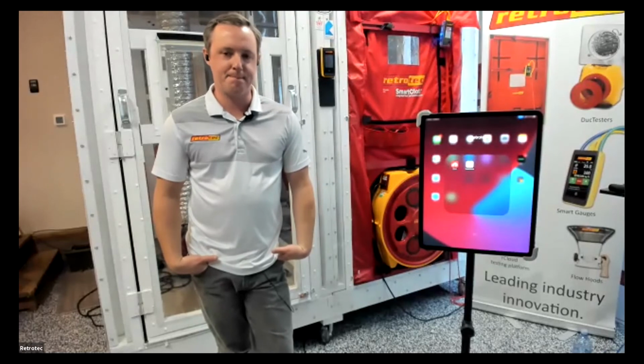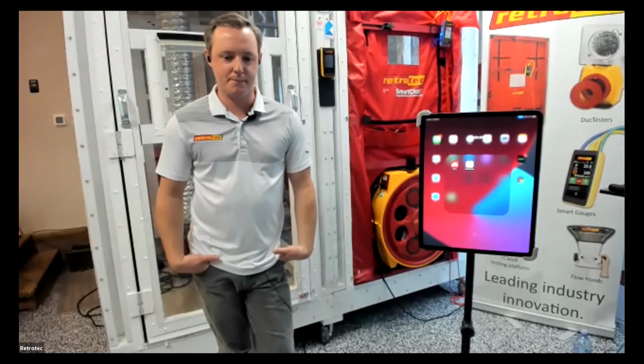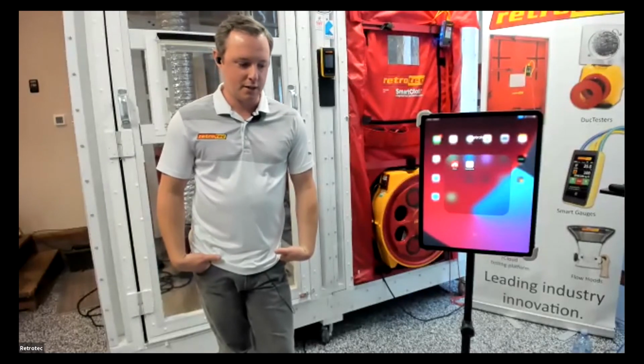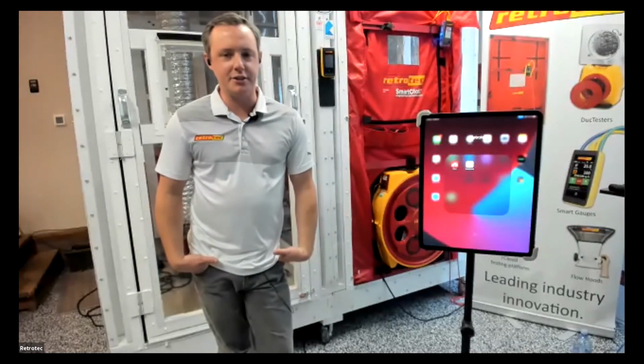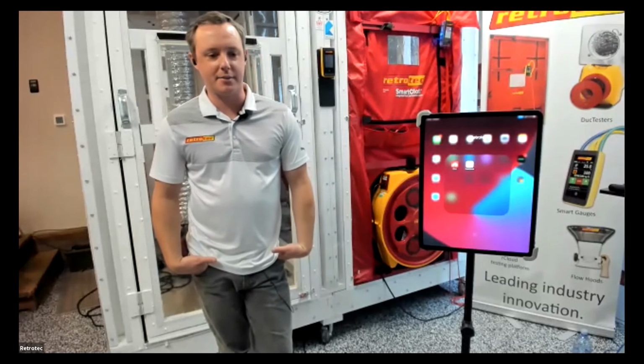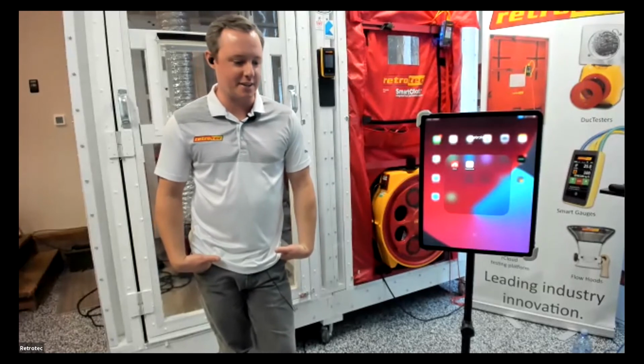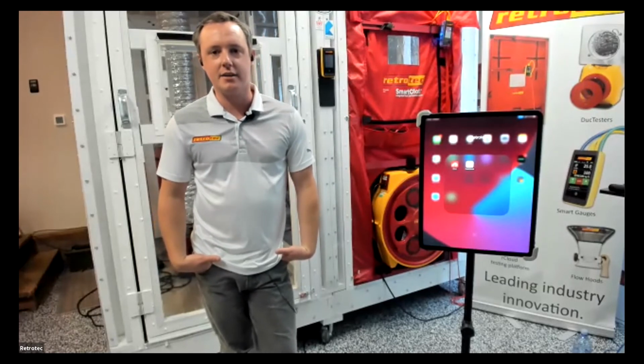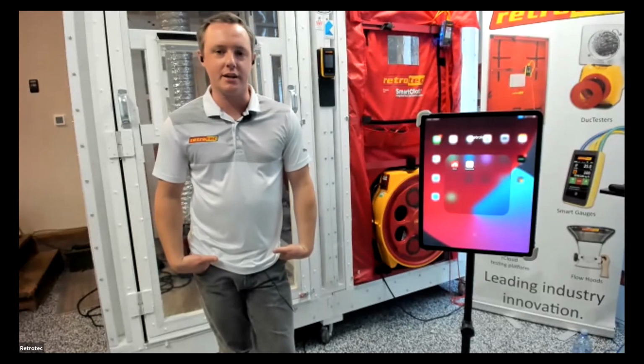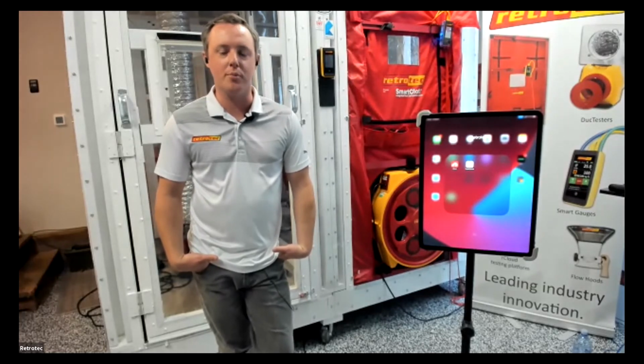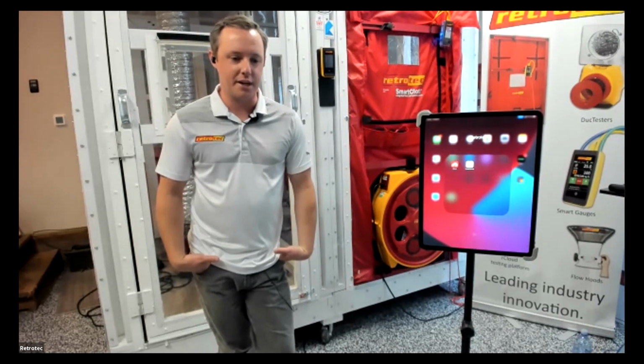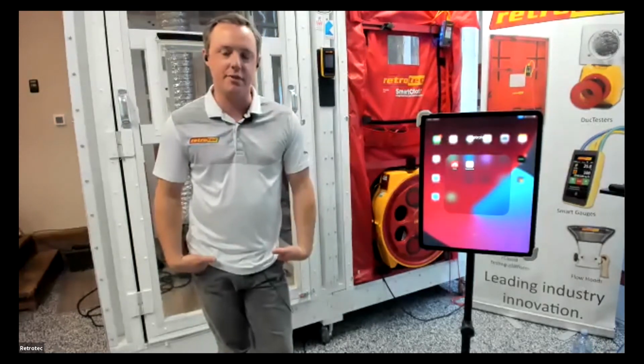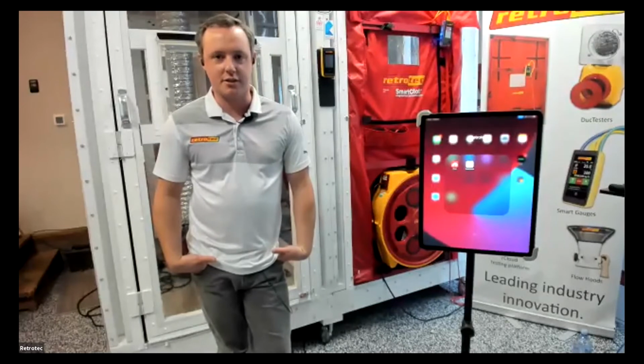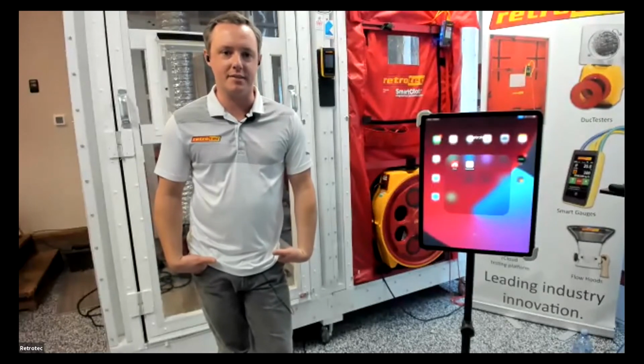Yep. We had a question here. Do you need to do a baseline on the blower door before you start when you're doing the duct leakage downside? Yeah, you should. That's something I should have covered. I kind of jumped into it to try to save time, but yeah, you should do that. And it's even more important here because it's even lower pressure that we're seeking, so any wind outside is going to have a larger effect. So yeah, good call. You do want to do a baseline reading on your blower door.